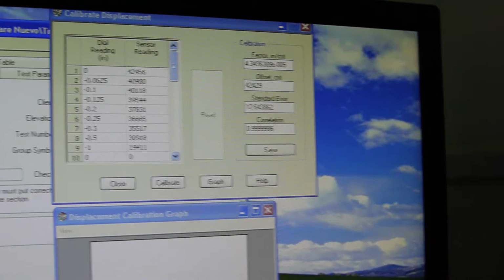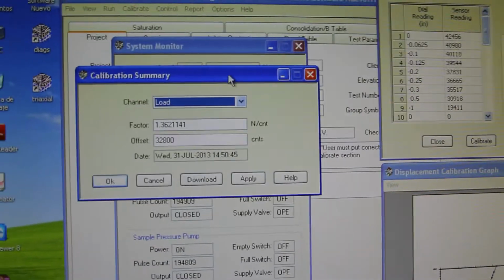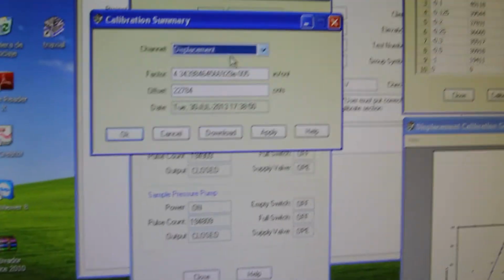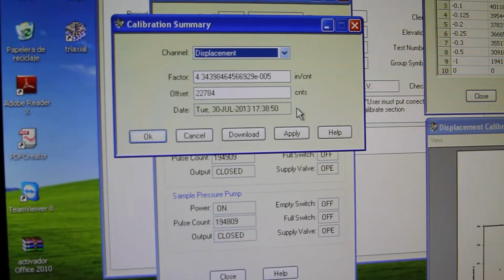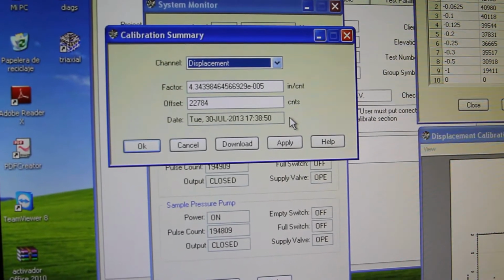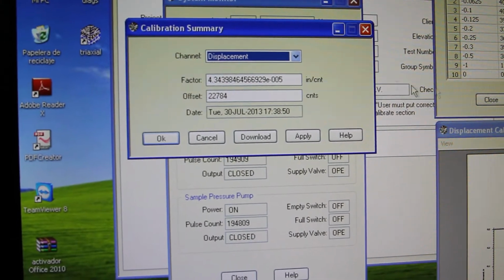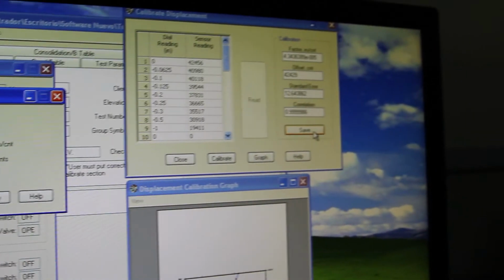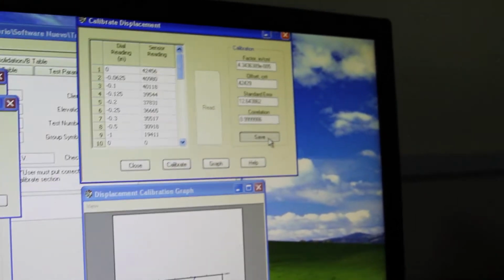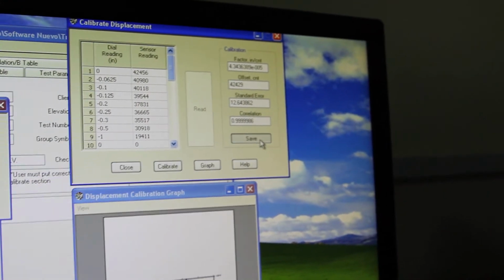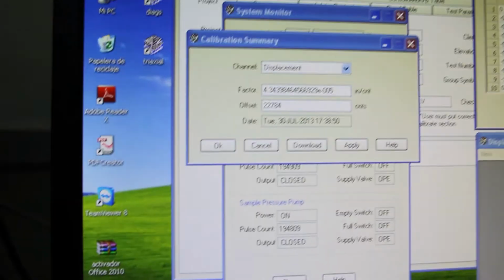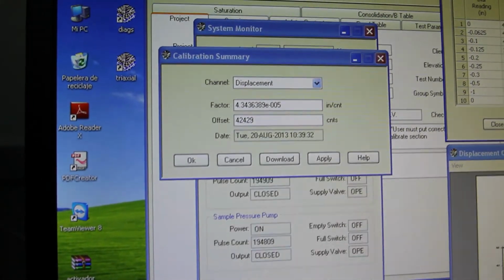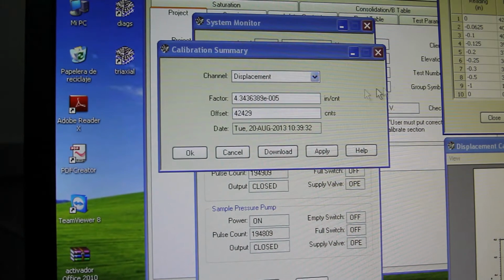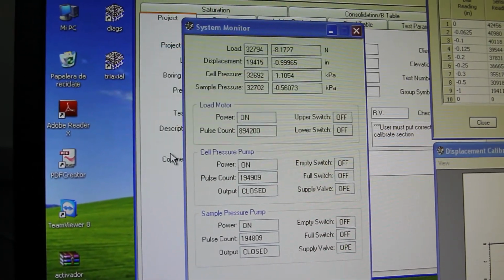So when I look at my summary here on my displacement, this is the old one that was done on July 30th, and this is the calibration factor. When I hit save in my Calibrate displacement menu, then the software will automatically take this factor and this offset, put them in here and update the date when it was done. So this is our new calibration, and you do apply and you do OK, and we're done with the calibration of the displacement sensor.